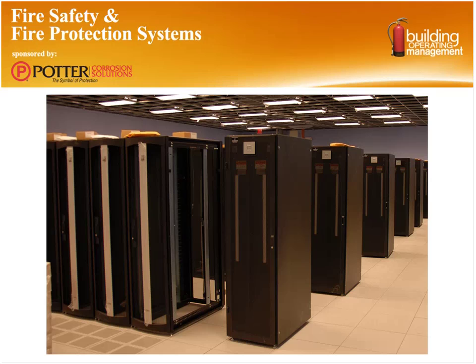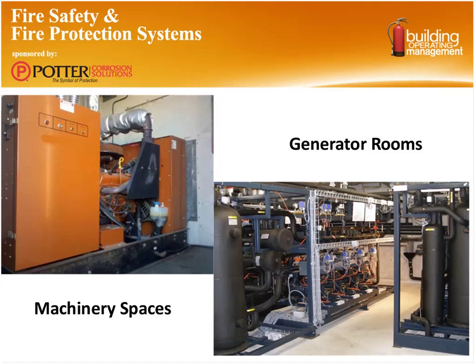Some extensive testing has been done by the military for machine space and electronic protection, and there are test results out there that you can find if you look at some of the Navy testing. Some other areas that we see fine water mist being used where typically other types of fire suppression would be used in the past, spaces like generator rooms over here, the generator space that we look at, or in machinery spaces. And in the past, a lot of those types of rooms would have been protected by carbon dioxide or just traditional sprinkler. And people are trying to move away from carbon dioxide fire protection in potentially manned areas because of the life safety issues of carbon dioxide being an asphyxiant.